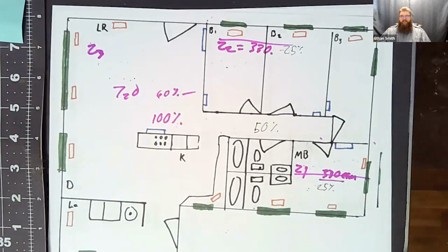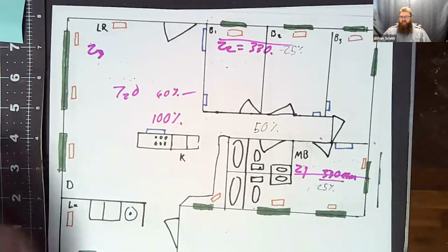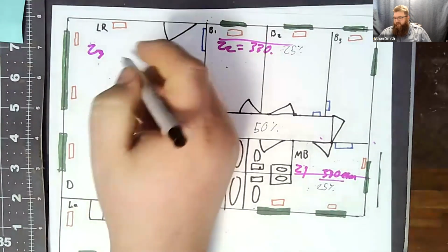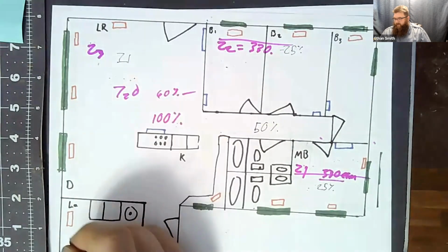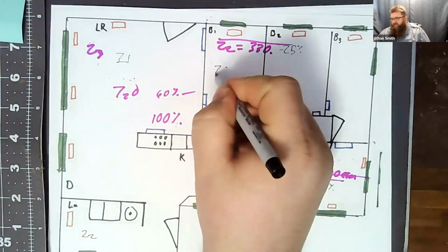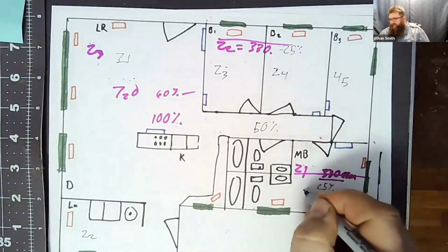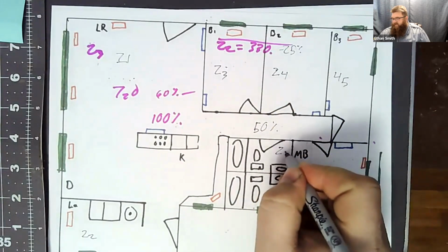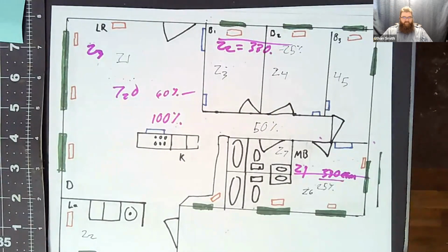But it also makes it really easy to shoot yourself in the foot. And the thing I see guys do the most that shoots them in the foot is they try to go zone 1, zone 2, zone 3, zone 4, zone 5, and zone 6. And I have seen guys zone a bathroom. 8x8 bathroom. It's on its own zone. Okay. That's where it all falls apart when we try to do too much.